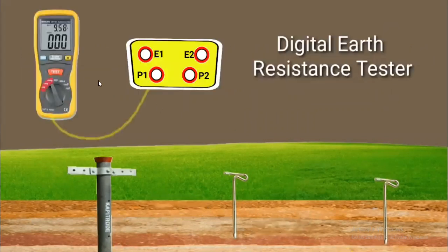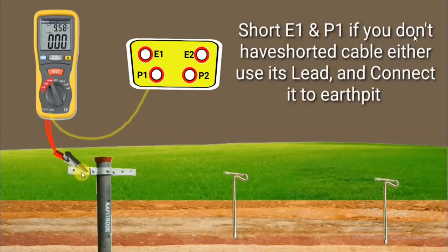So next is the digital earth resistance tester, by which we can measure the value of earth resistance. It basically has 4 terminals, located at the bottom of the tester: E1, E2, P1, P2. For the measurement of earth resistance, we have to short the E1 and P1, if they are not already shorted. With the help of a cable, we short the P1 and E1, and then the shorted lead is connected to the earth pit, for which we have to measure the resistance.